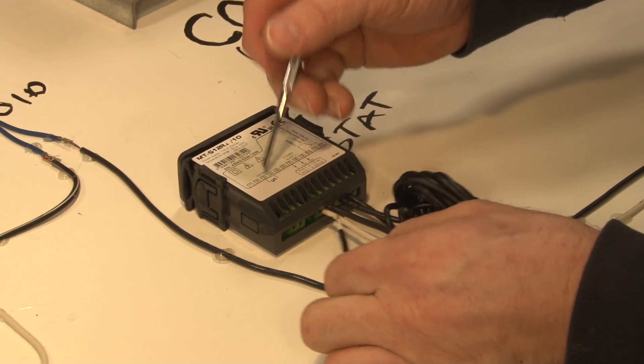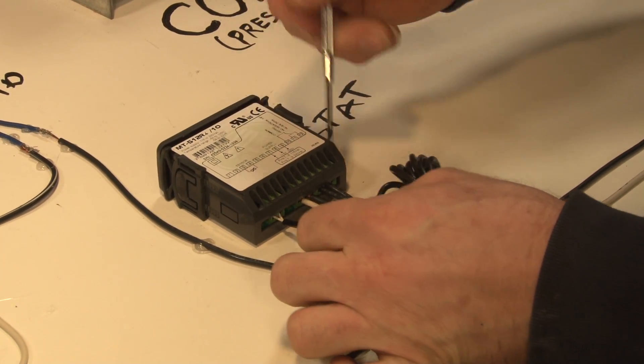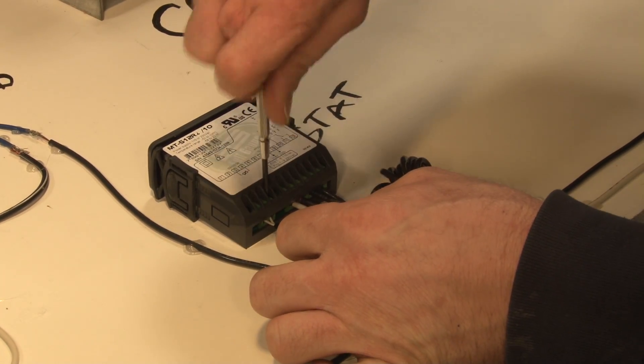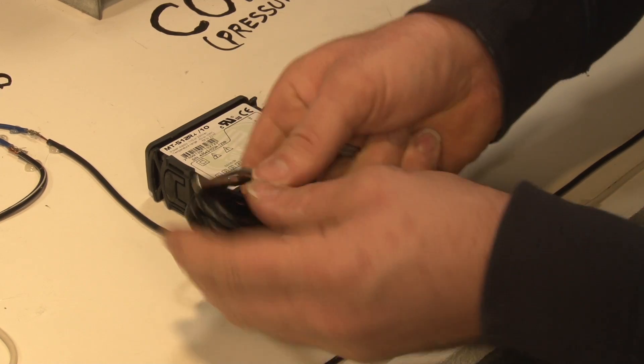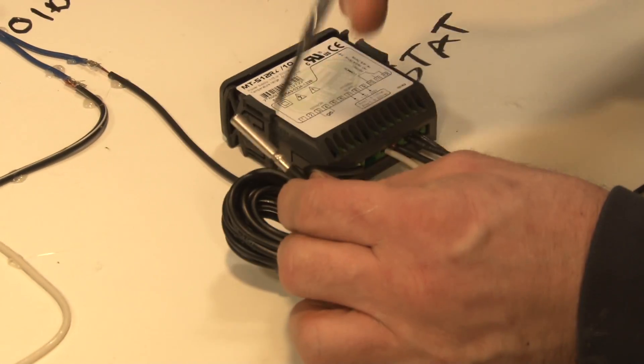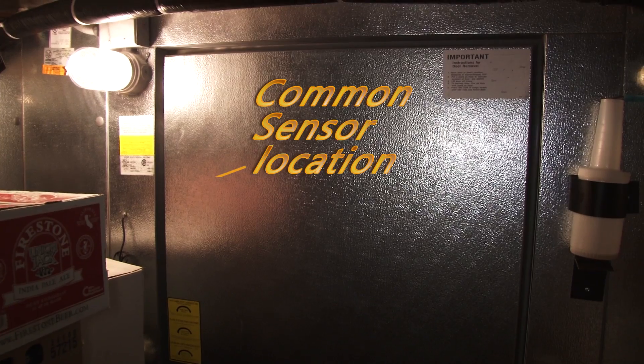And it's pretty easy. It just goes right in these two sensor terminals like all the other wires. Tighten that down. And this is our ambient temperature sensor. This we can mount anywhere in the back of the evaporator coil or anywhere in the cooler box.